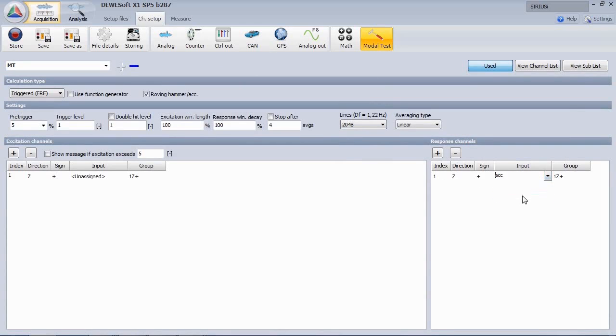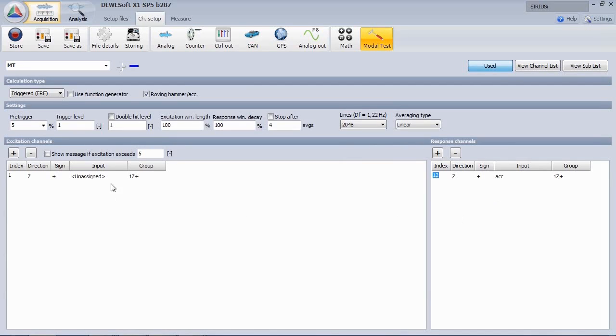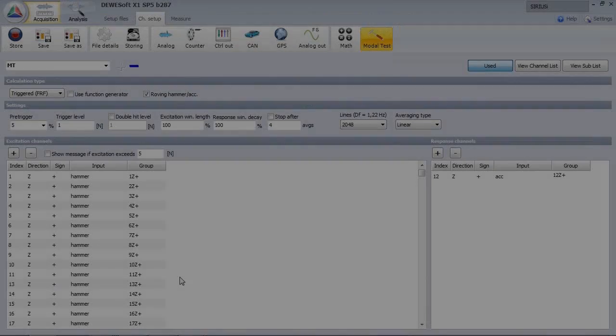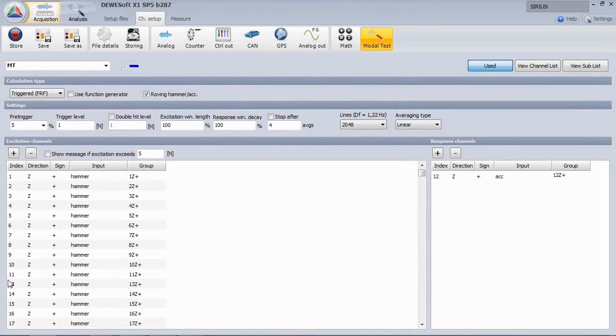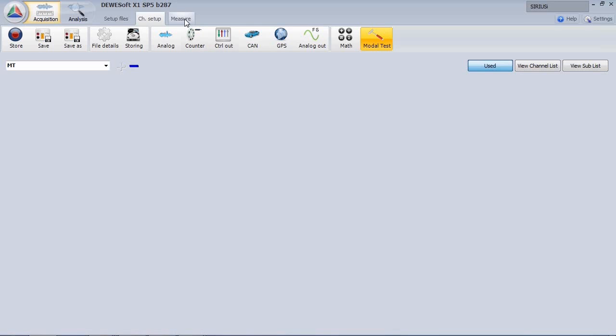The response channel is our accelerometer mounted in point number 12. As the hammer is moving through the points, we have to define all excitation points. After we have done that, note that point number 12 is not present on the left side. It doesn't make sense to knock directly on the accelerometer.